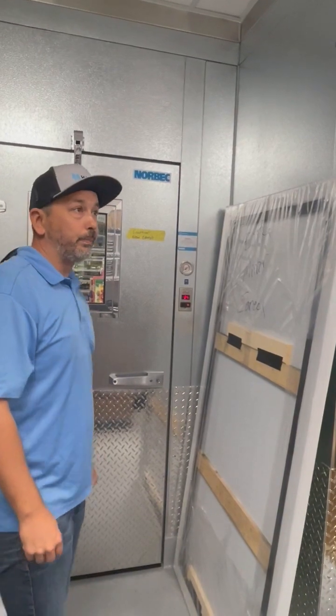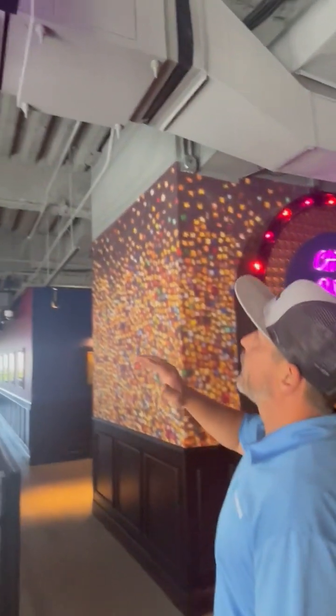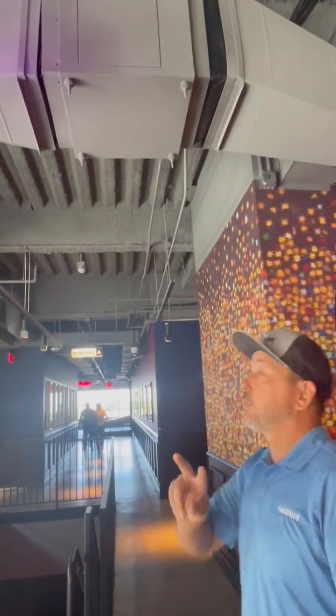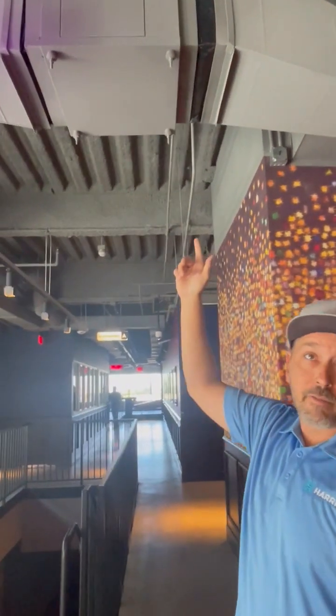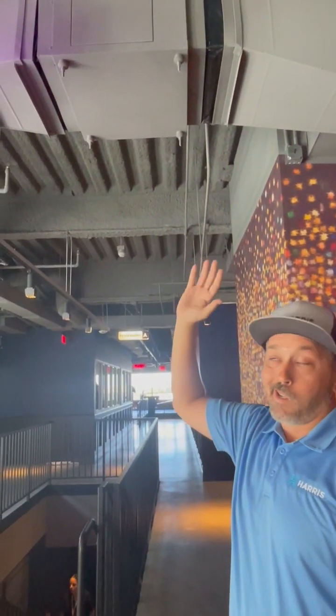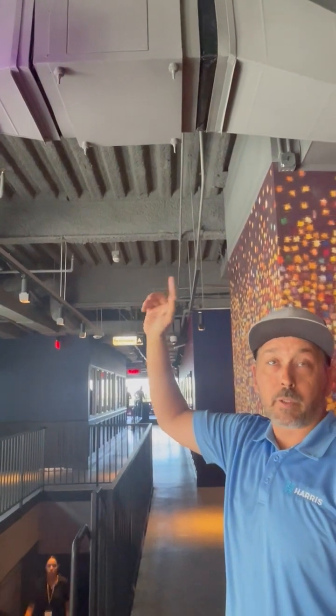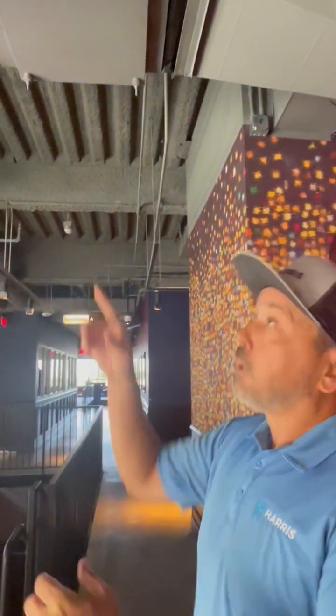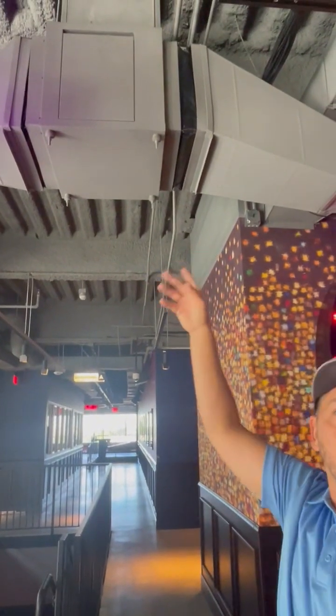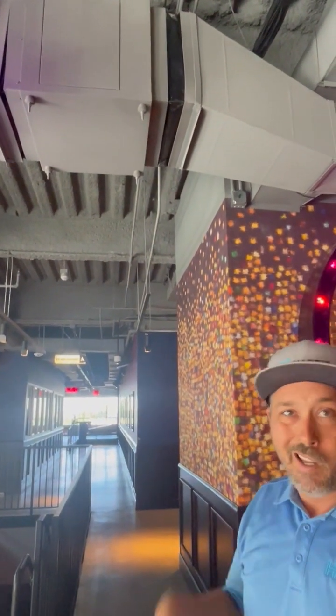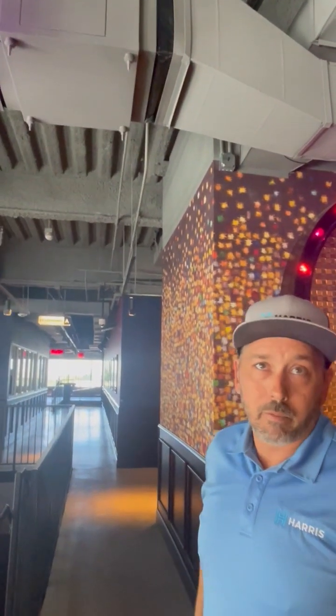So, the exhaust fans in this space - I believe there are two - are inline fans with a belt on them, which we can get you the size for. That's the only thing you'd have to check on these. If these fans aren't running, the belt's slipped. To check the belt, you pull out the side panel right there and observe the belt. If you're not getting air, call us or call somebody, but it's a belt issue.